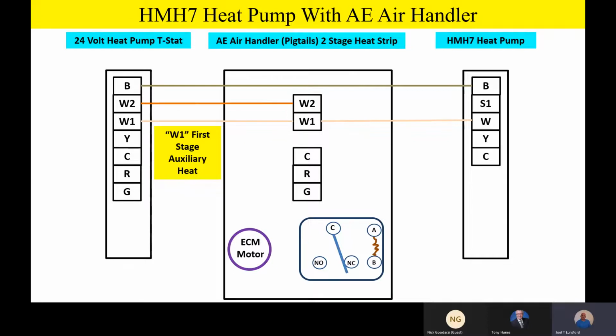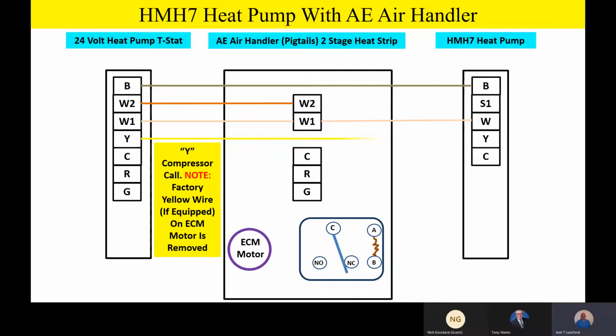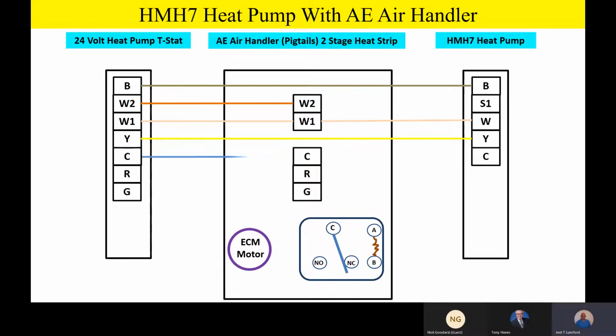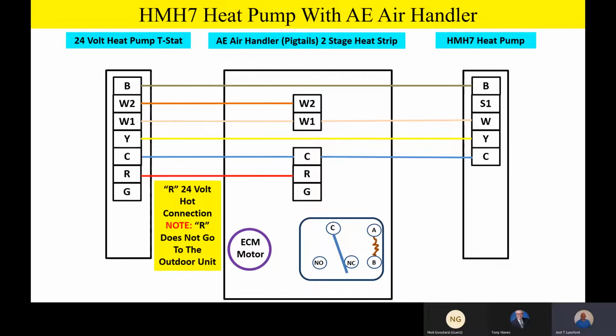Because remember, team, when the unit goes into defrost, it's actually going into the air conditioning mode. And so if we have a heat pump out there and it goes into defrost, we want to make sure we have some auxiliary heat on as well. The Y terminal is going to go straight outside. The C terminal will tie in to the air handler and then go outside as well. That'll go all the way through. And then the R terminal is our 24-volt hot, powering up the thermostat.